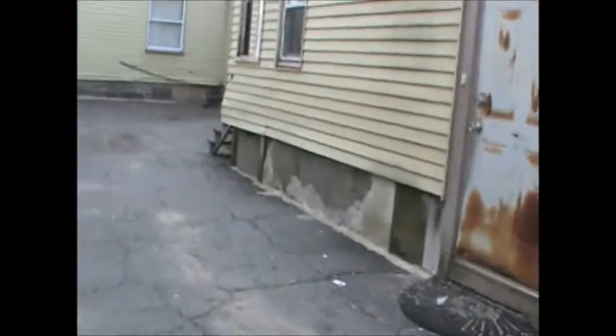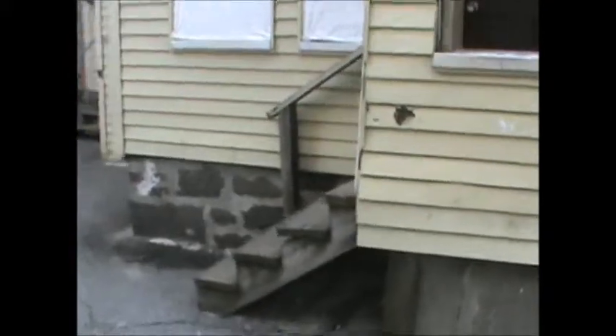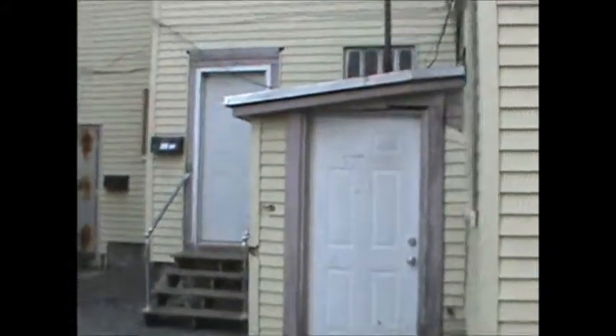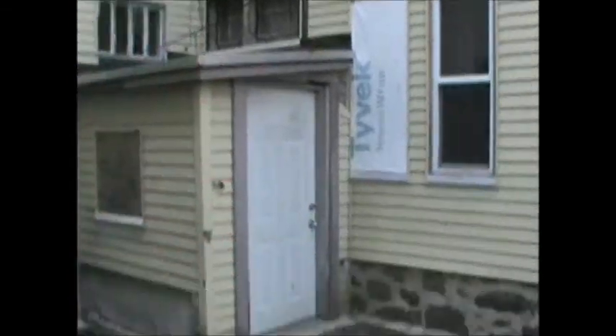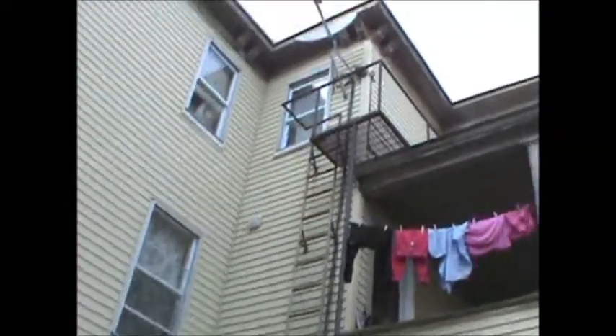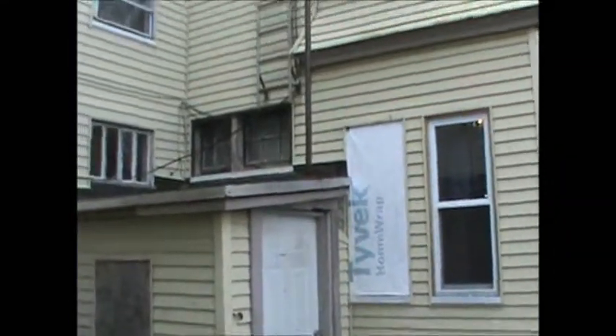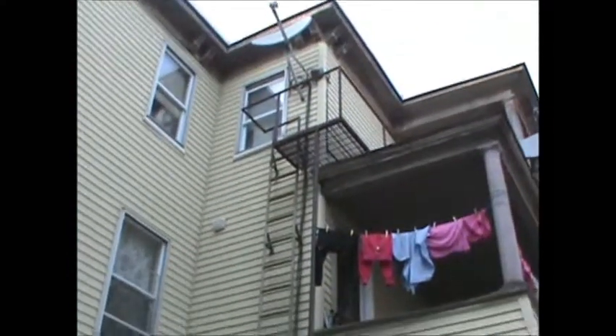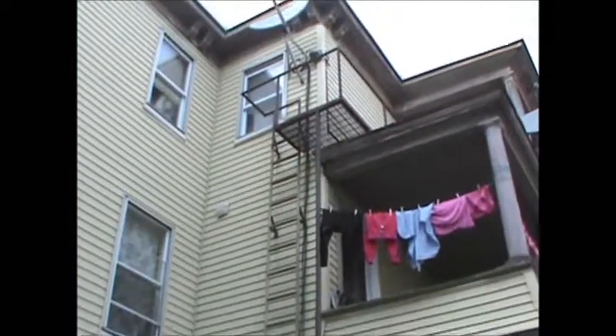We also have this here that needs to be addressed, and also any staircases as to whether or not these are going to be considered fire escape systems as part of the inspection. So we have these here also, and there's another fire escape back here. So this will be determined with the city official, and there's another fire escape right there that we need to discuss whether or not that is incomplete to grade. As you can see, a fixed ladder with a platform that picks up that corner. So now we need to determine, but it must land on another catwalk system here, and then that catwalk system must put the people to the ground either with a full staircase or with a ladder, if the city official allows a continuation to grade with a ladder, fold-out ladder, or a staircase.